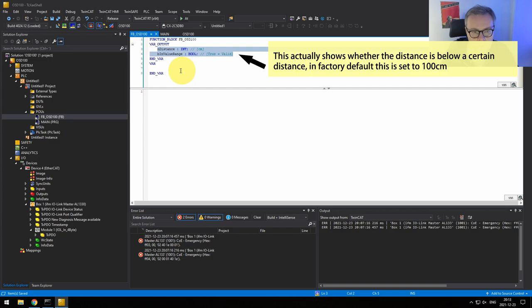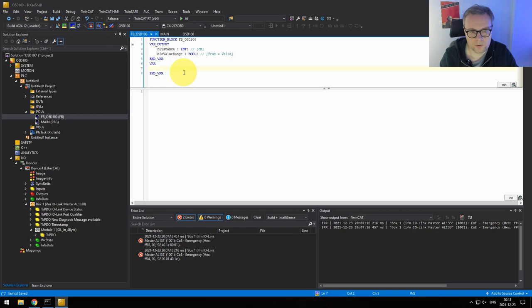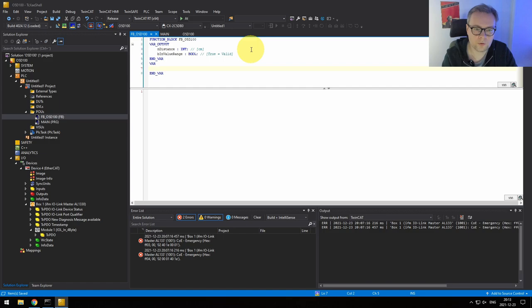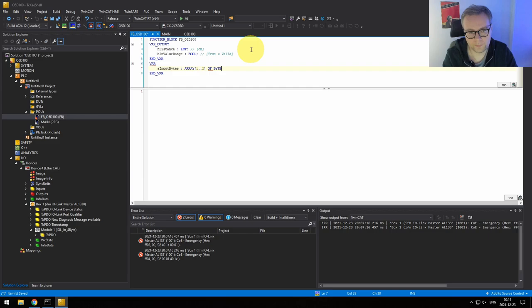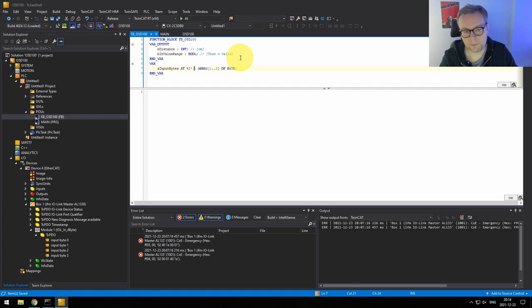We've defined what we want out of the function block. Now we need to link these bytes and convert them to values. We'll declare the 2 input bytes using the %I* syntax to make them linkable in the process data image. So we declare aInputBytes as Array[1..2] of BYTE at %I*. This means when we compile, we'll have 2 bytes in the process data image that we can link to the hardware. Then we need to instantiate the function block in the main program and compile.